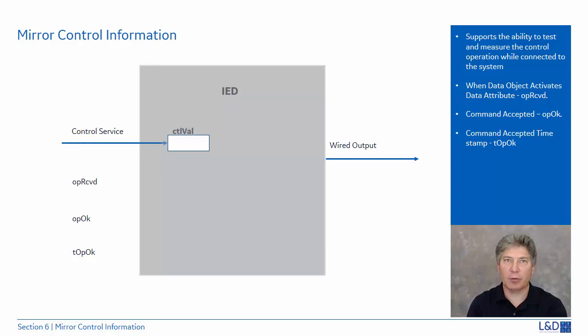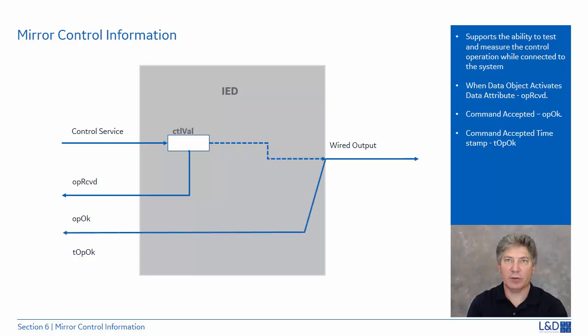A control command is applied to a controllable data object. As soon as the command has been received, the device shall activate the data attribute OPReceived. The device shall then process the command. If the command is accepted, the data attribute OPOK shall be activated with the same timing as the wired output. The data attribute TOPOK shall be the timestamp of the wired output and the OPOK signal. These data attributes are produced independently of whether the output is wired or not. The wired output shall not be produced if the function is in mode test blocked. They therefore allow an evaluation of the function, including the performance, without producing an output.